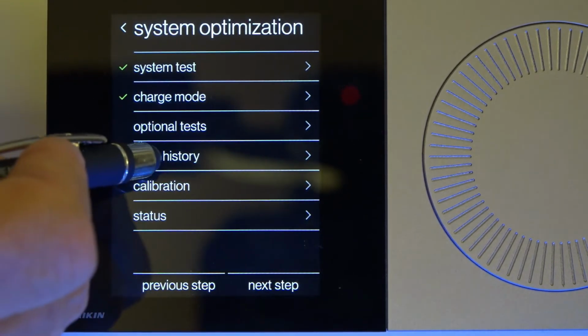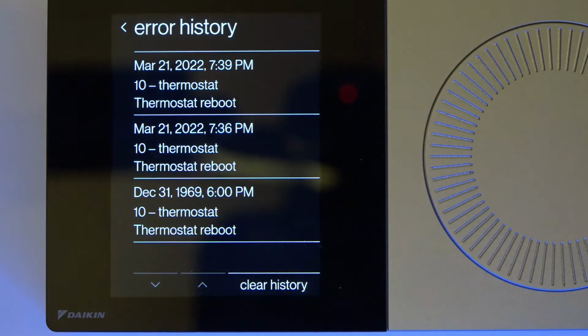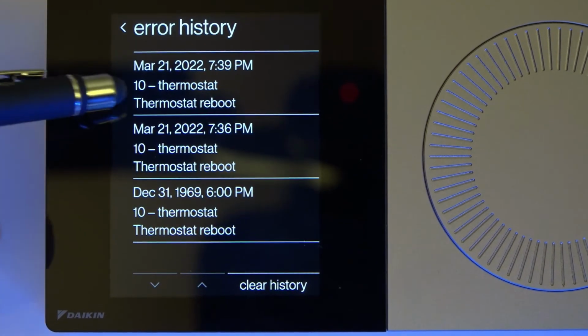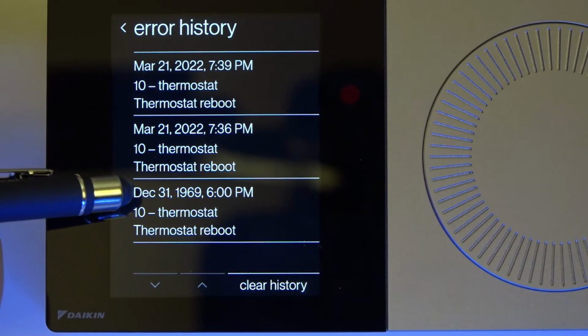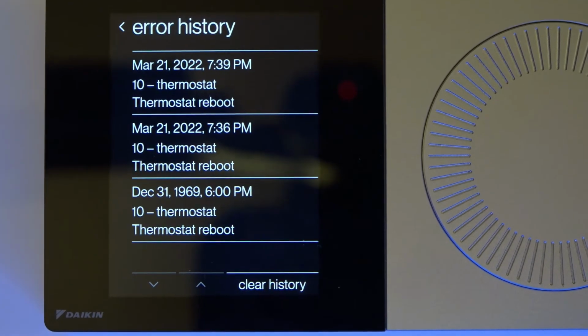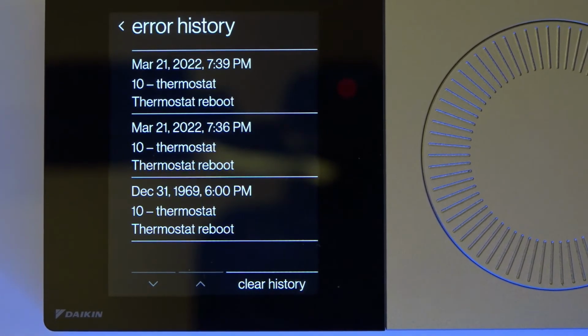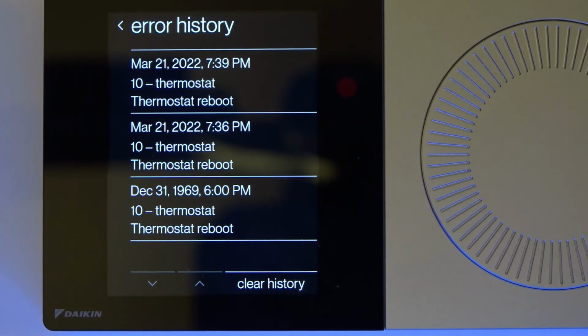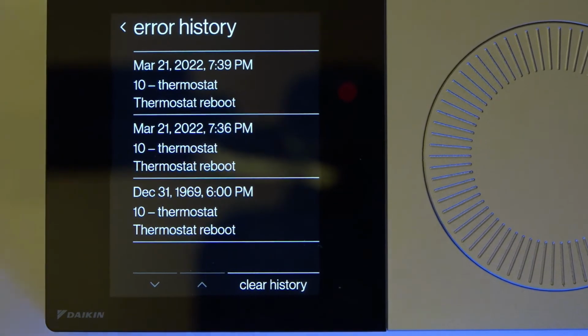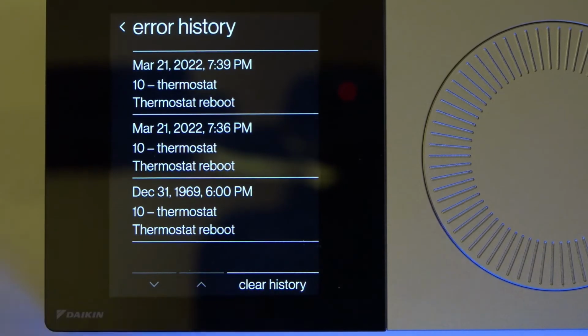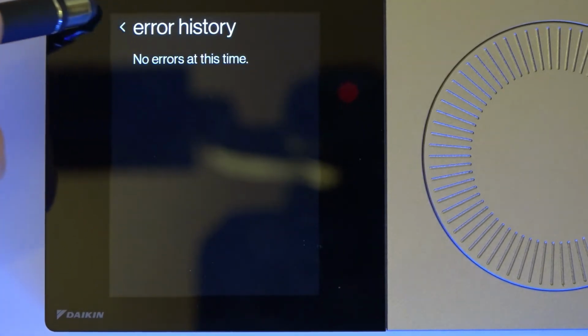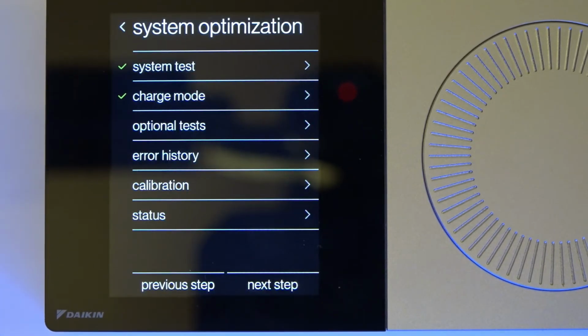So as I'm testing things out, I might have created an error. If my errors are in white, it's a non-critical error. That means the machine saw something it didn't like, it made a correction and kept on going. If you have a critical error, then that critical error is going to be in a yellow letter, and that means the machine has shut down and we need to figure out what those are. But when you're done, just hit clear history, continue. Okay, no errors are found now, so we can back up out of this.